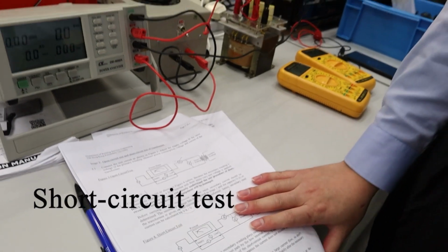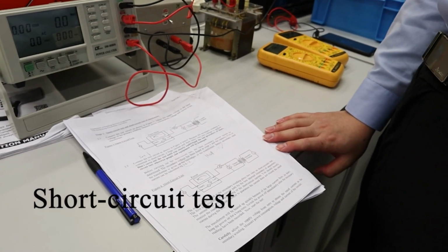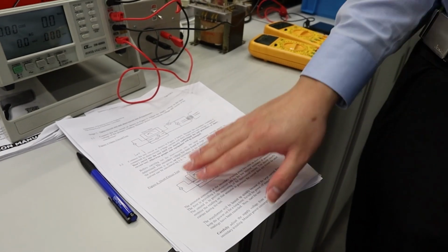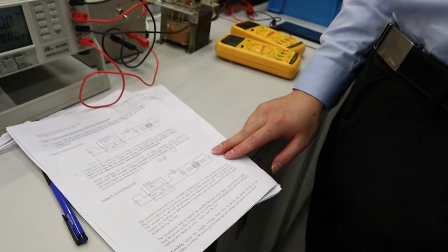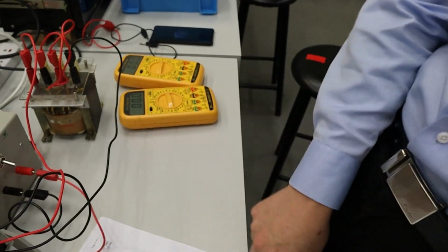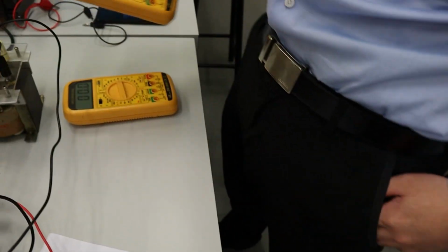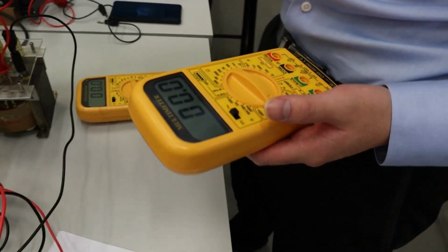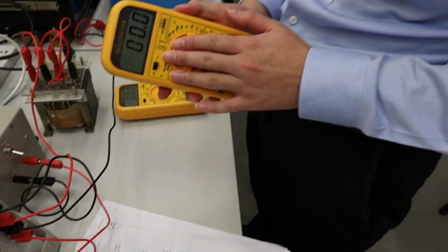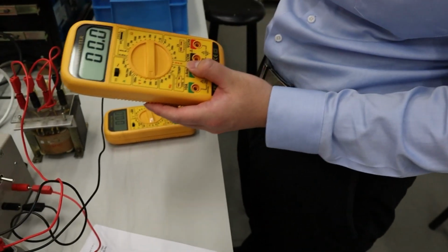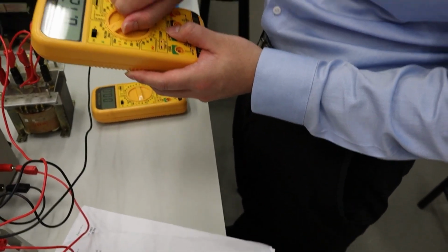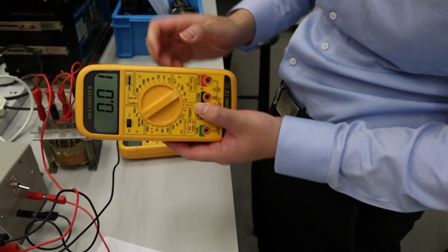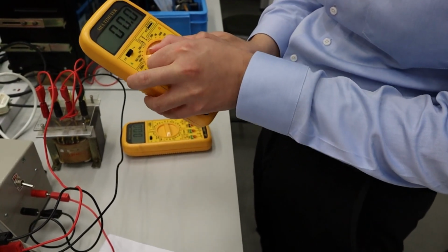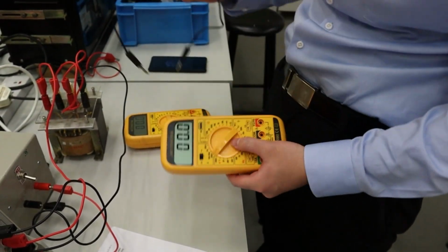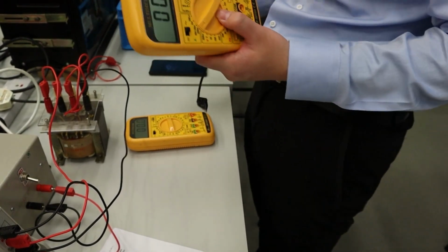We are going to do the short circuit test. The difference between the open circuit test and the short circuit test, as I have mentioned, is that on the secondary winding we need to connect a current meter. So we are going to use a multimeter, and change it to measure the current here, then connect it to the second winding.